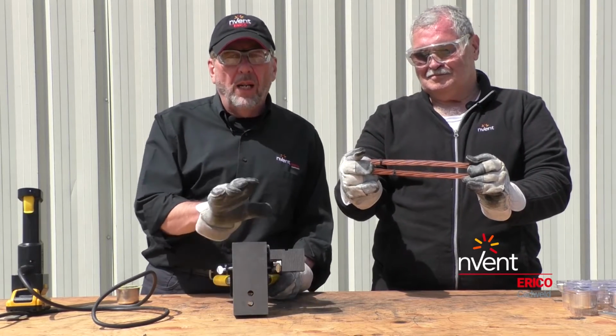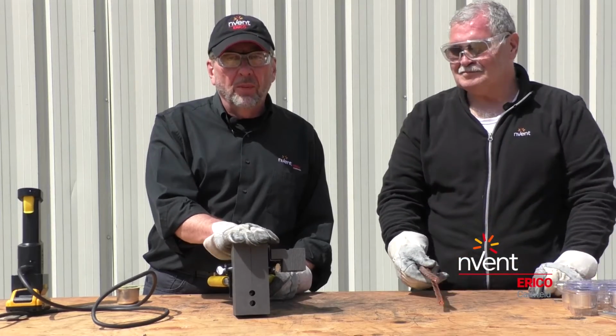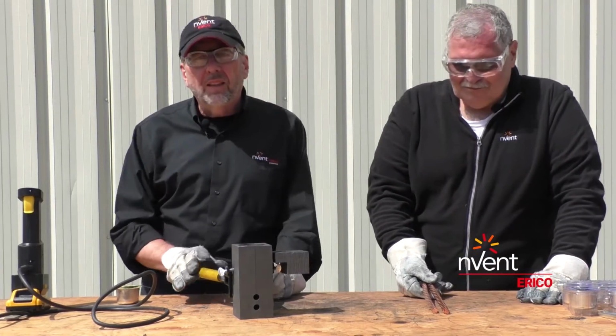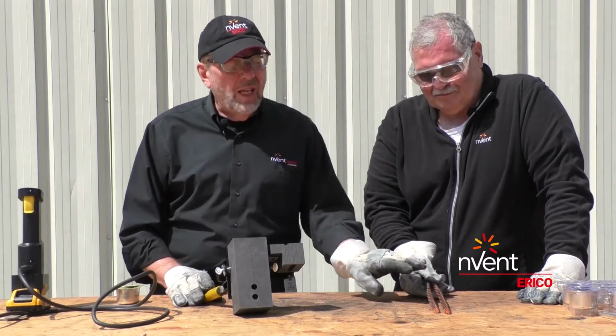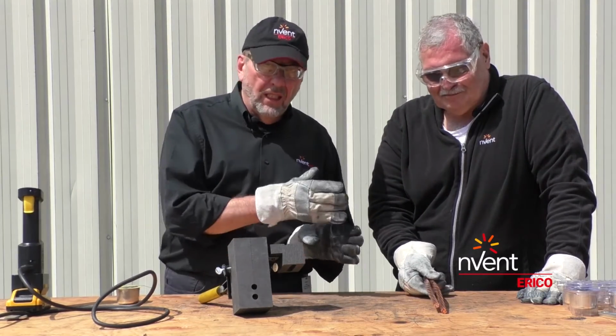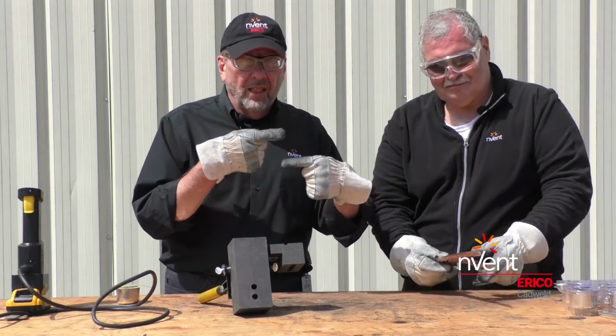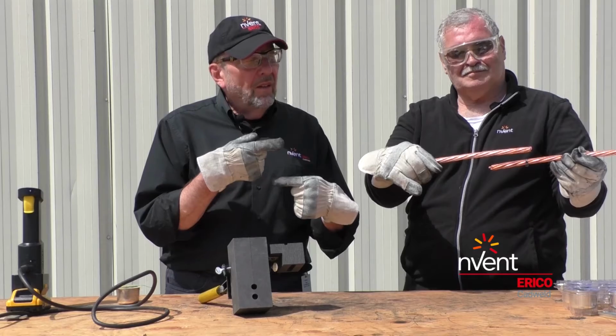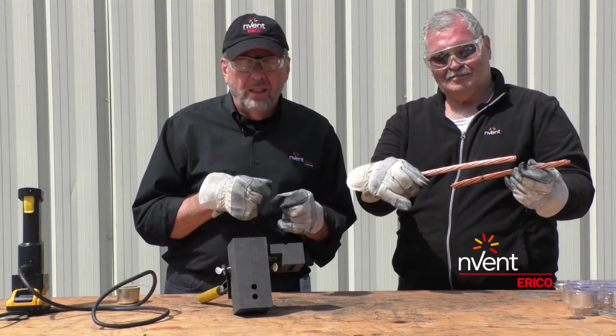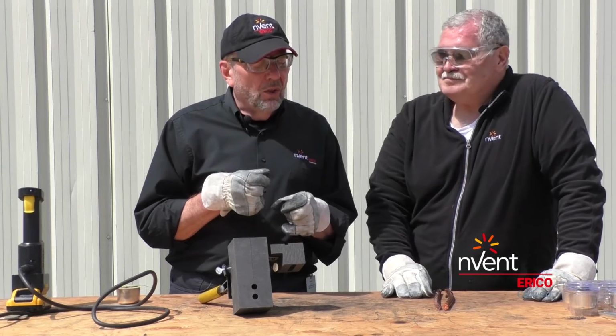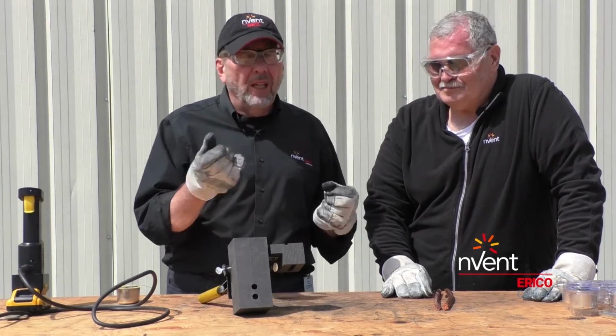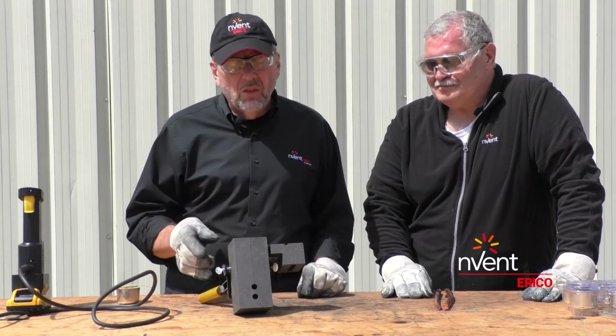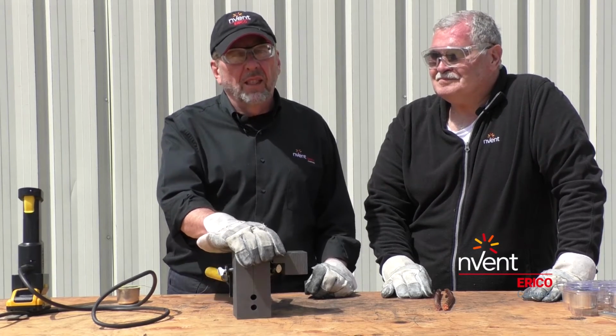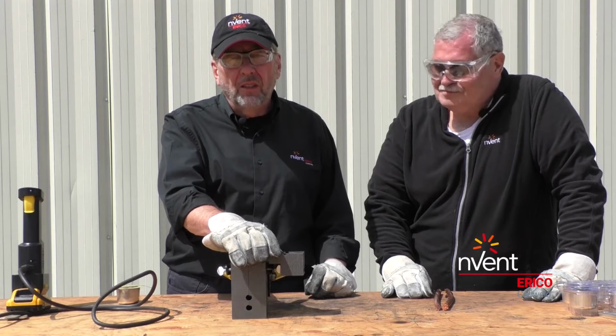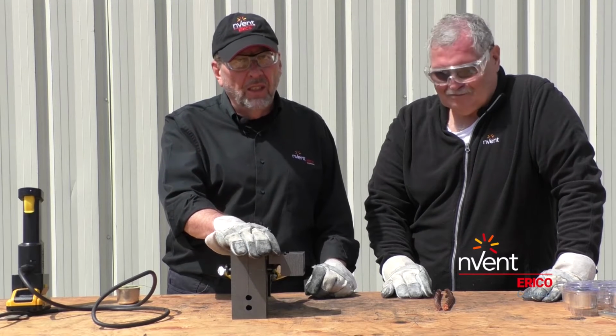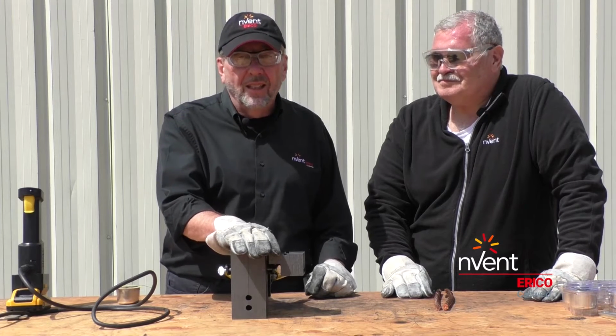This mold represents probably the most versatile connection type that we offer. If I'm willing to be clever with the conductors as I'm making this connection, I can make the PT connection where they're one above the other. I can offset them and make a straight splice. I can take the top cable and bend it to make a TA connection, or I can bend the top cable and the bottom cable in opposite directions and have an X. So if you're looking for a mold that does a whole bunch of things in one block, the PT mold is the answer to that need.